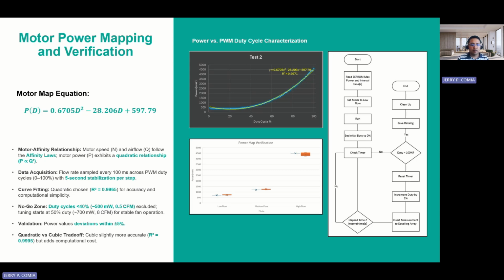In addition, I've identified a no-go zone for duty cycles below 40%. In this range, the fan behavior was unstable, leading to poor repeatability of the airflow. This instability made the system unpredictable and not suitable for reliable operation. As a result, we decided to start tuning at a duty cycle around 50%. At this point, the fan operates in a more stable region, where the system's performance is more consistent and predictable. This choice ensured that we get accurate airflow control without unpredictable variation.